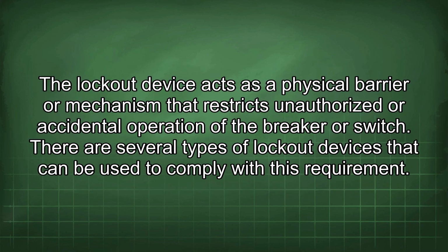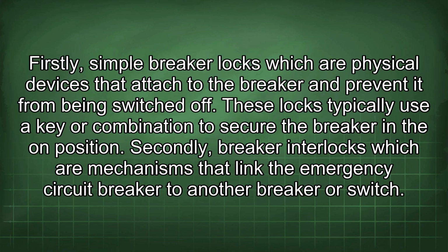The lockout device acts as a physical barrier or mechanism that restricts unauthorized or accidental operation of the breaker or switch. There are several types of lockout devices that can be used to comply with this requirement. Firstly, simple breaker locks, which are physical devices that attach to the breaker and prevent it from being switched off. These locks typically use a key or combination to secure the breaker in the on position.